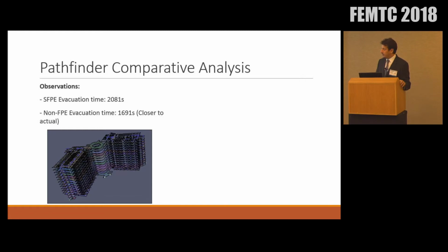The SFPE evacuation time was about 2,100 seconds, and the non-FPE evacuation was about 1,700, which is actually closer to the actual evacuation of 1,200 seconds. So the non-FPE evacuation time was more accurate. Doesn't mean it's correct or not, but I'm basically showing the benefit of looking at other studies and what people are doing. As a student, when I was doing my studies, we never looked at other non-fire protection studies. We only focused on the fire protection studies.